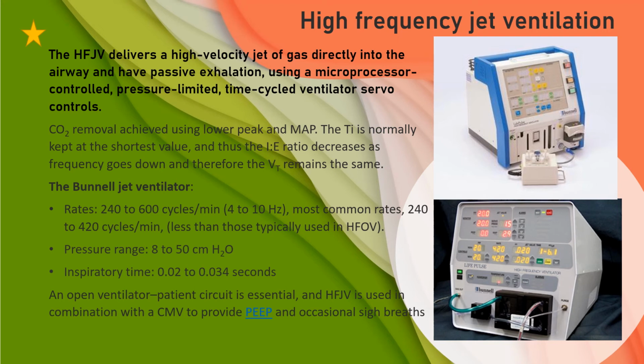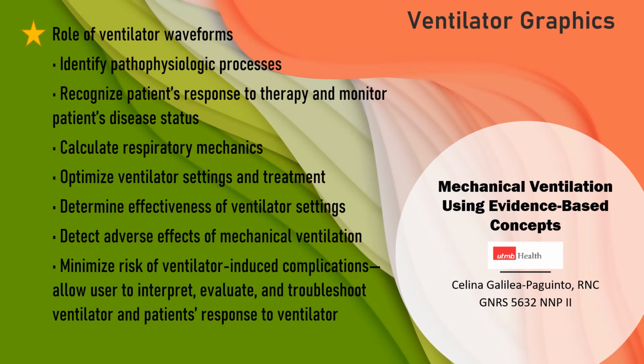The Bunnell jet ventilator is started on settings of 240 to 600 cycles, or an equivalent of 4 to 10 Hz. Most commonly, our neonatal population is started at 240 to 420 cycles, less than those typically used in the HFOV. The pressure ranges from 8 to 50, and the I time is started at 0.02 to 0.034 seconds. An open ventilator patient circuit is essential because HFJV is used in combination with a CMV to provide PEEP and occasional sigh breaths. Why is it necessary to recognize ventilator graphics?